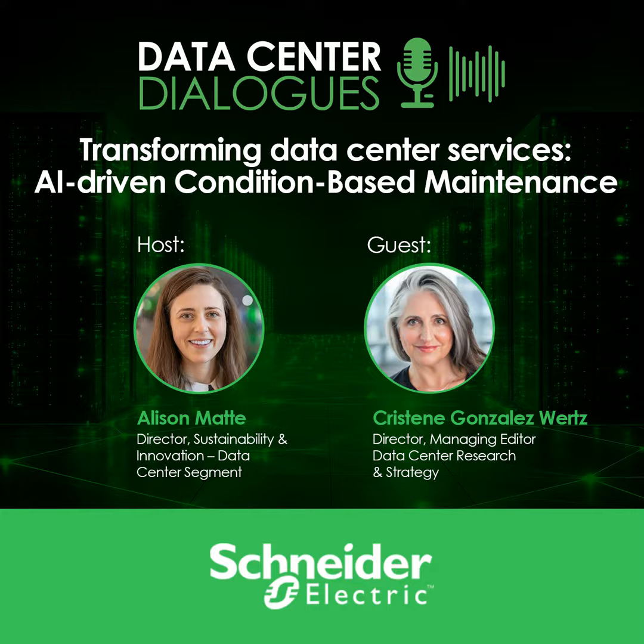Before we jump in, a quick distinction. Our 2025 report, Transforming Data Center Services: AI-driven Condition-Based Maintenance, draws a line between asset-level monitoring and systemic condition-based maintenance. Asset-level monitoring tells you how one UPS or cooling unit is doing. Systemic condition-based maintenance, or CBM, looks across power, cooling, and IT load together, so you can detect risk earlier and prioritize the right intervention.